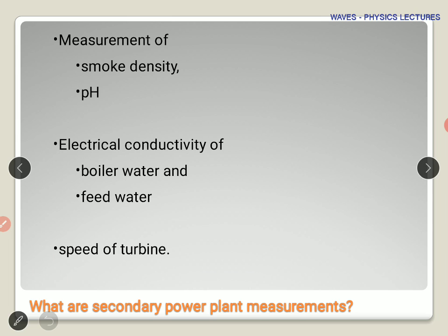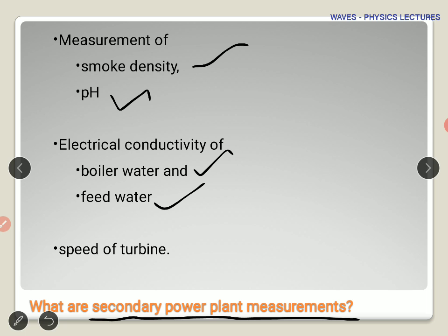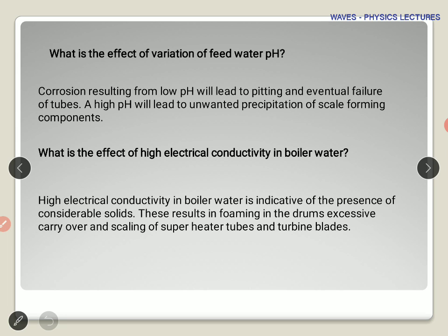Secondary power plant measurements include smoke density, which can check pollution levels and engine efficiency. The pH value of the water flowing through the system also needs to be monitored — it should be more or less neutral, as pH affects electrical conductivity. The electrical conductivity measurement of the boiler water and feed water, and the speed of the turbine, also fall under secondary power plant measurements. These are equally important, just classified separately.